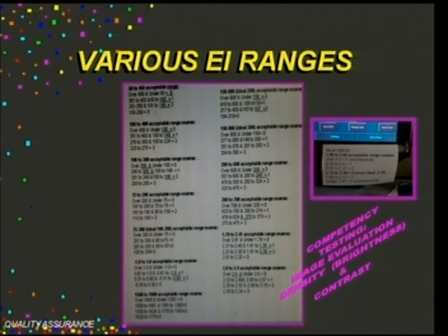And we say, this is where I work, 2.12 to 2.24 is the most ideal place that's dead center. And the dead center number that the students wanted to know, because they want to be that precise, is 2.18. When they can get it on 2.18, they're all high-fiving and getting all excited. But the technologists are also looking at that. And they have now gained back that visual connection between what they're setting on the control panel and what they're delivering to the patient. And they're seeing what changes they're making at the control panel.